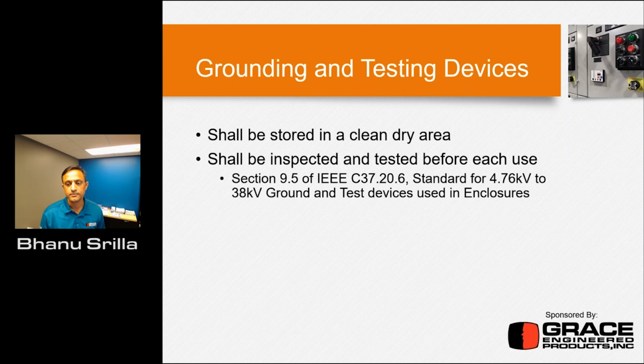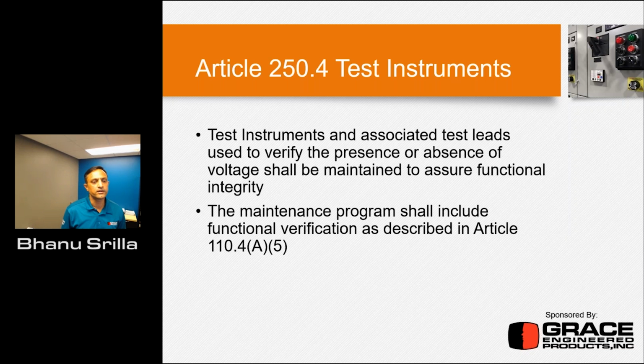Okay. So the next one is Article 250.4, test instrument. This is one of the favorite areas where Grace plays significantly, using the portable test instruments for absence of voltage or presence of voltage testing. This applies to portable test instruments, specifically if you're using this device for verifying the presence or absence of voltage, it has to be maintained to assure the functional integrity.